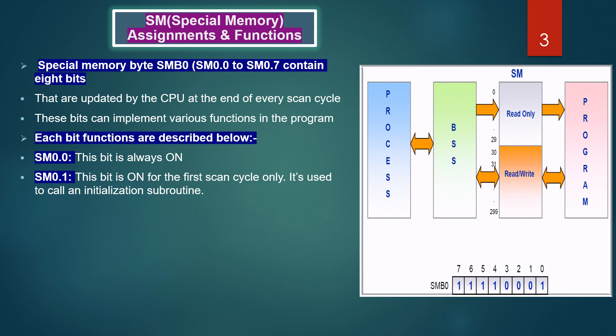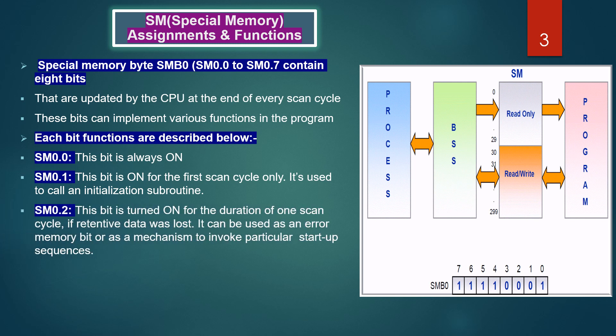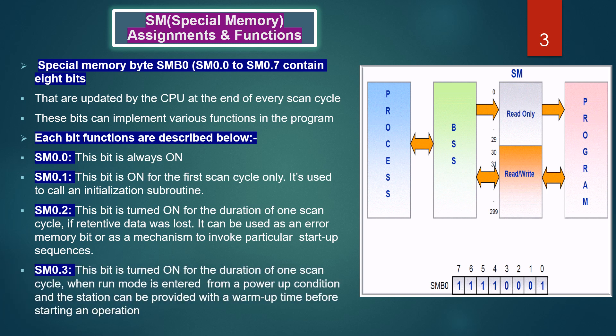SM 0.1: this bit is on for the first scan cycle only; it is used to call an initializing subroutine. SM 0.2: this bit is turned on for the duration of one scan cycle if retentive data was lost. It can be used as an error memory bit or as a mechanism to invoke particular start-up sequences.